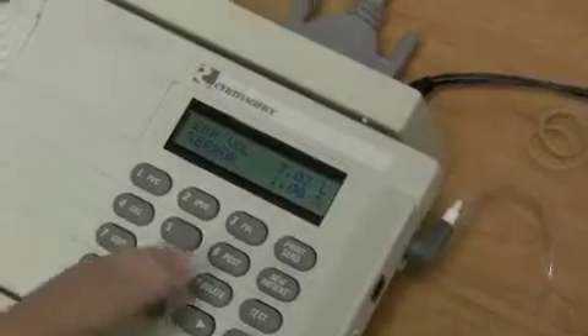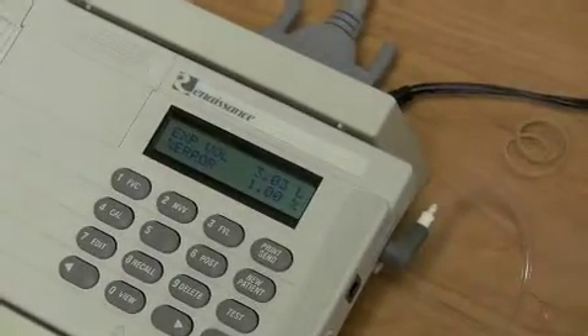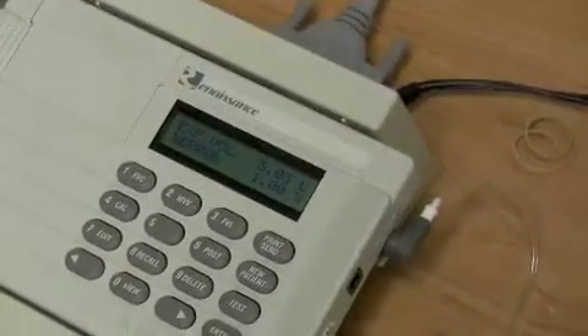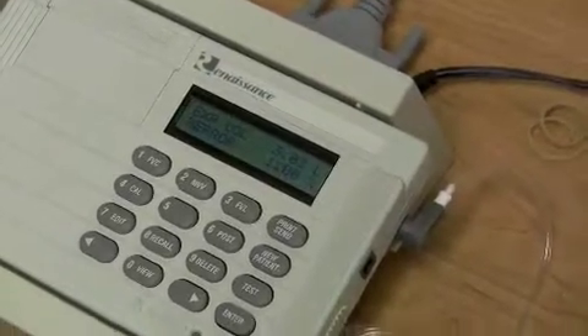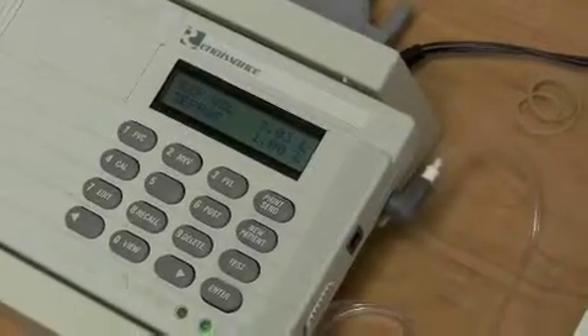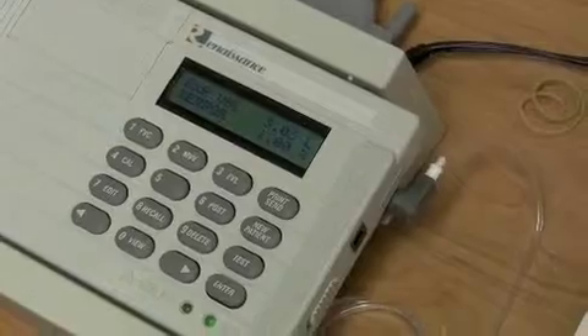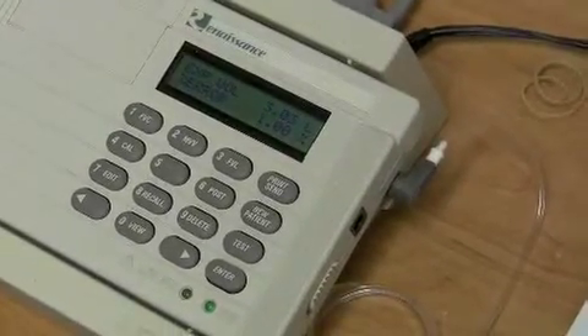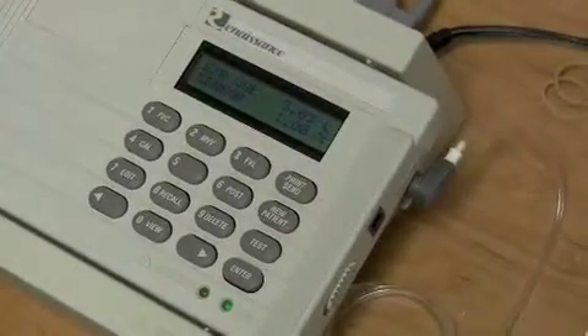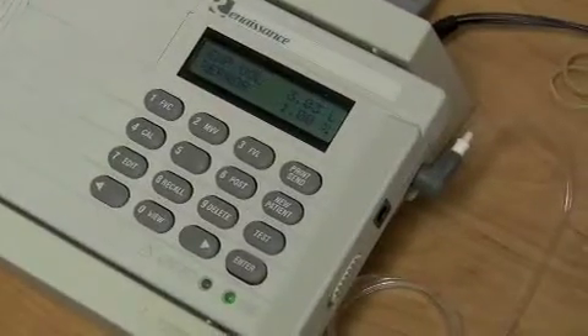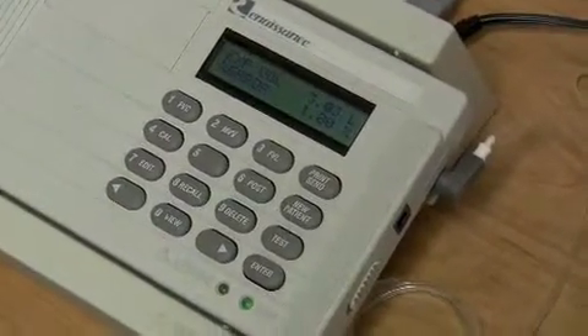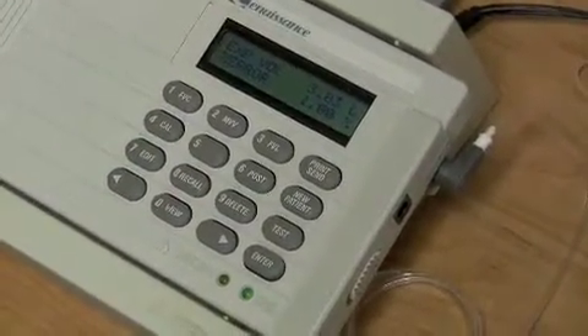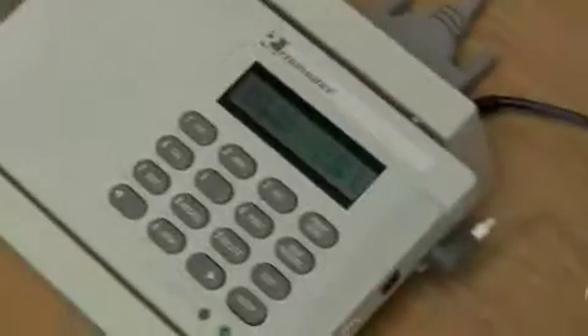As long as you're in 1%. You see it's giving you expiratory volume. The cylinder is known to be 3 liters, and this gives you its percent. It gives you what it measured, here in this case 3.03, and percent error, which here is 1%. That is correct. And the maximum allowable is 5%? Is that correct?